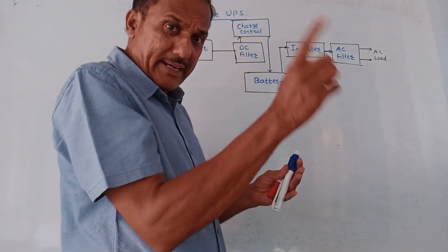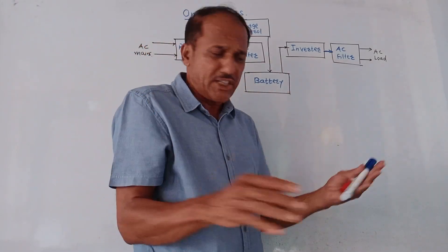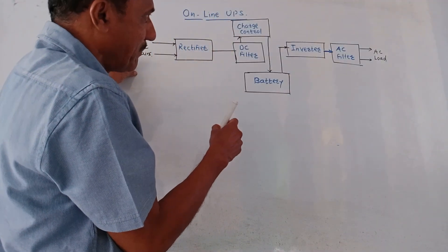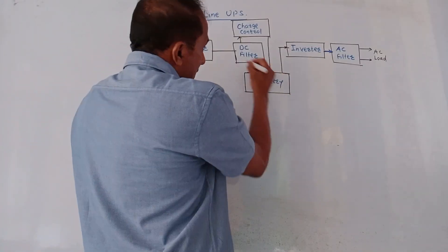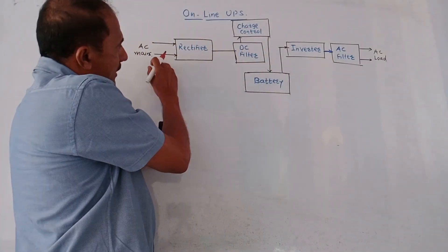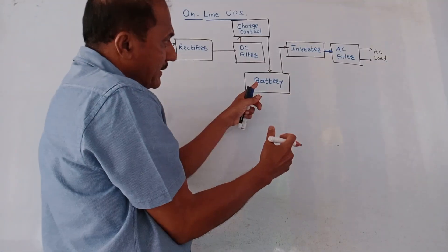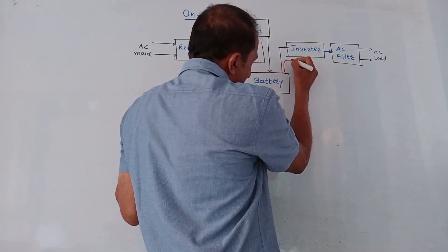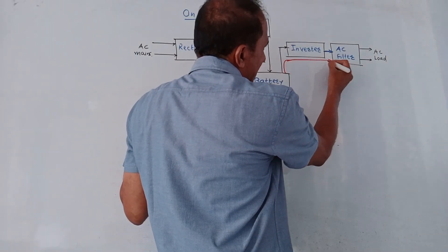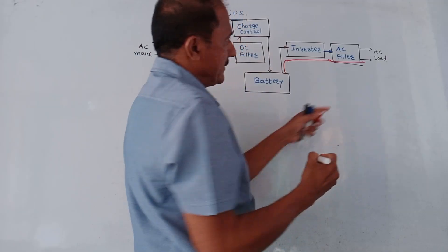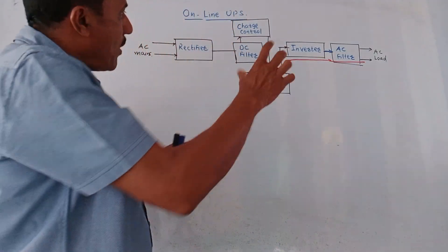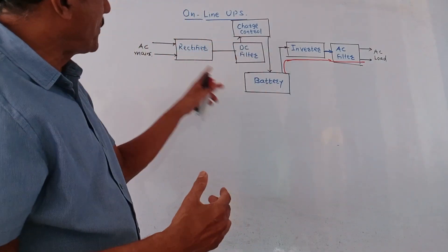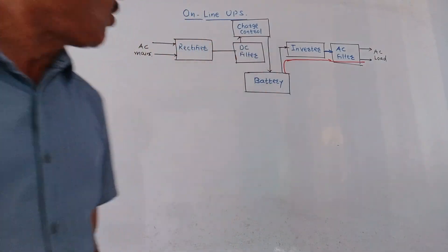Whenever there is a power failure, no switching action is required. When AC mains fails, that circuit goes off, but the battery has stored energy and is directly connected to the inverter, then to the filter, and then to the AC load. So the power supply is continuous. Ideally there is zero switching time, and this type of UPS is called online UPS.